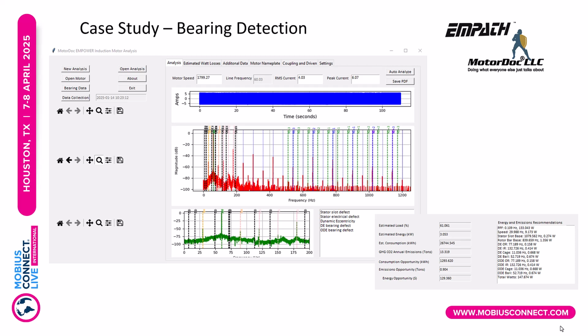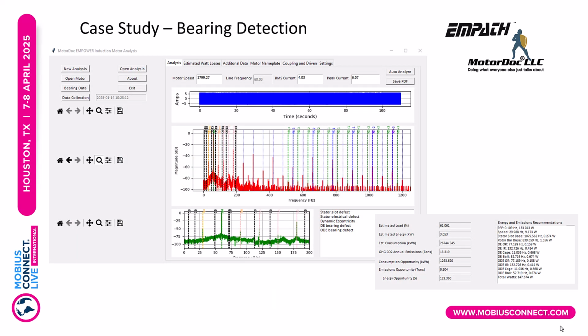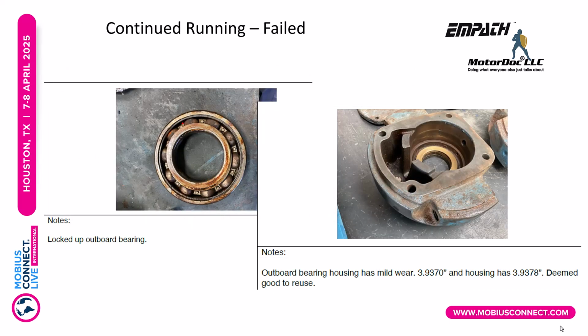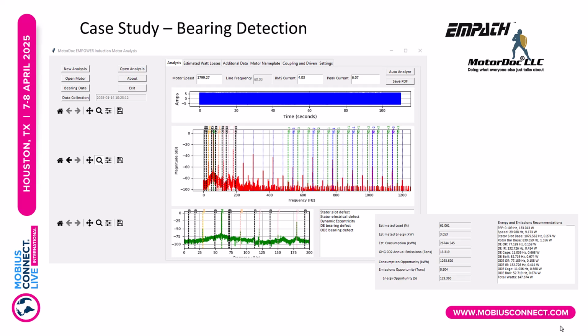So here's a bearing detection on a machine, a 60 hertz machine. It's operating, and if you look on the right, we can see a very, very low watt rating. So that one there, if you can see, it's primarily on cage. So we say, okay, that's the motor bearing, maybe some lubrication. But they heard a bearing noise. Turns out to be on the pump. So the bearing defect in this case has to do with the lubrication, but the other reading that we took, and this was done under the coupling and driven portion, where we looked at the conditions of the pump itself, is we did identify a dry bearing that ended up locking up on them. It's not in the calculation here, but it is most definitely one of the things that was picked up.